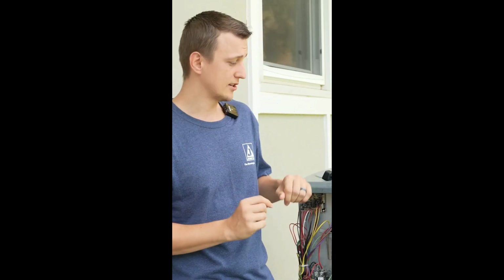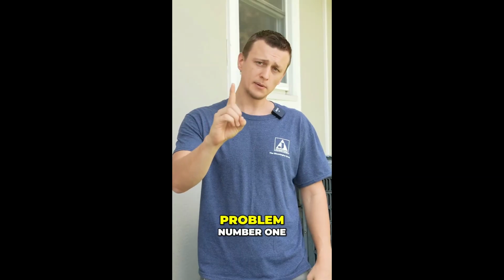Or maybe it is cooling off, but it just never reaches the set point. If you have your thermostat set to, let's say, 75, it never gets there. It just hovers around 78 and it struggles to go down. That could be a sign that your unit is low on refrigerant. But before you jump to that conclusion, one thing I would try doing is washing down the condenser unit. It might be dirty.